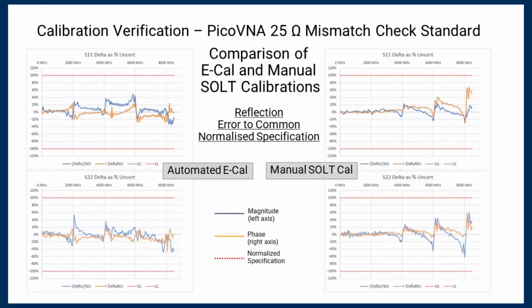So on the left here I've got my reflection parameters plotted for magnitude and phase within the spec bounds. And this data on the left is from the automated eCal that I performed, and on the right I've done exactly the same process. I present the data for the manual calibration that I performed. Now you can see that both sit well within specification, and I'm very glad of that.